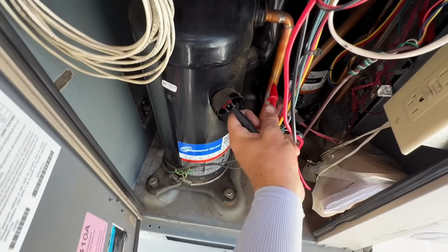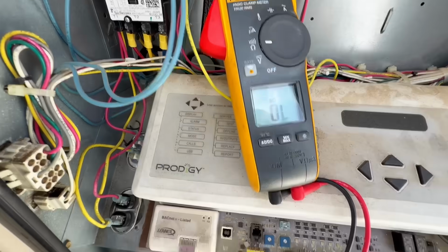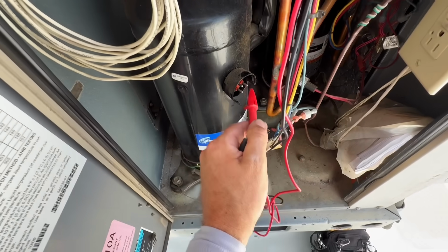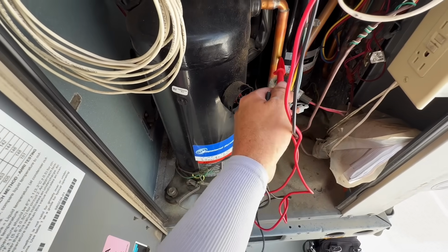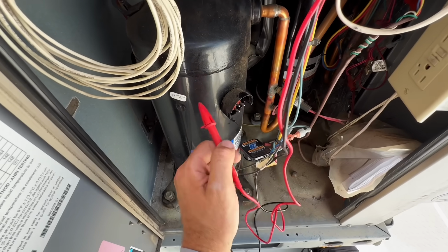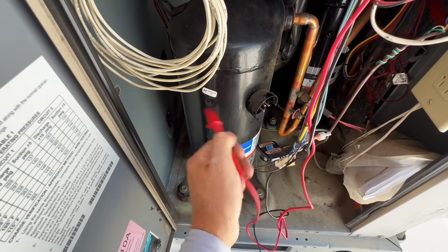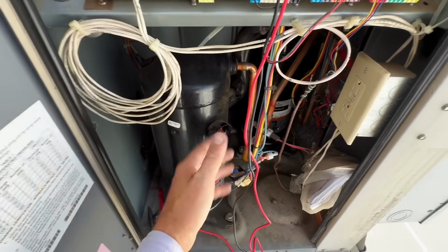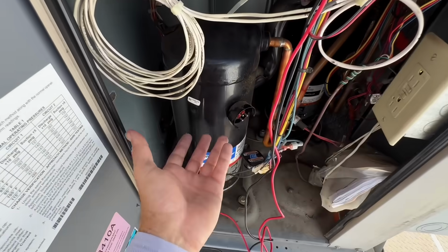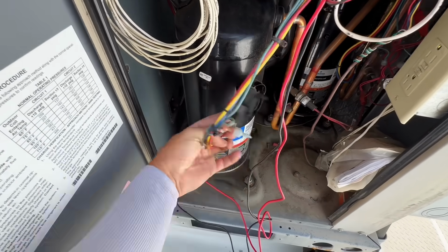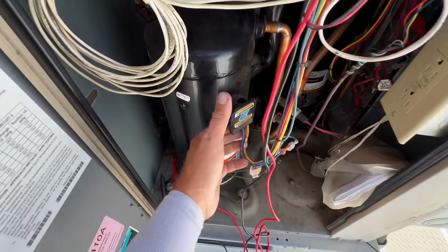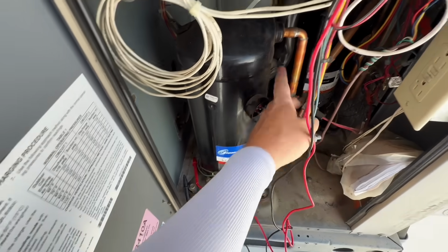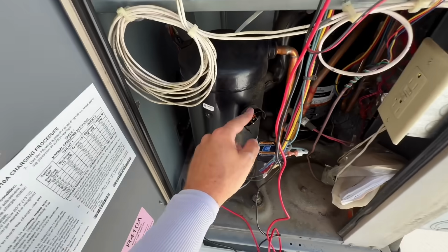It doesn't look like we're reading resistance to ground, but this is why it's good to have a mega ohm meter. So you can put one on the terminal and then connect it to ground and apply voltage to see if the insulation might be damaged internally. Because with our windings reading open, we would not be tripping the breaker because there's nowhere for the electricity to flow, so it would just never start up.